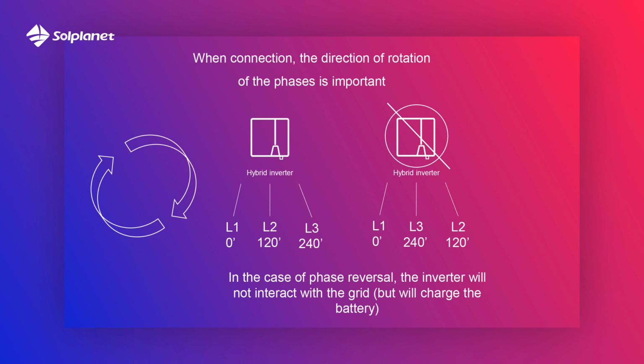If the phase sequence was incorrect and we changed the phase sequence on the inverter socket, remember to change the current transformers accordingly. If we change the phase sequence in another place after current transformers, we don't have to replace the current transformers.